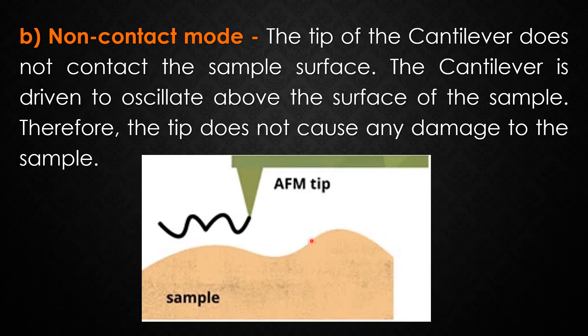Next is the non-contact mode. In non-contact mode the tip of the cantilever does not contact the sample surface. The cantilever is driven to oscillate above the surface of the sample, therefore the tip does not cause any damage to the sample. In non-contact mode the driving motion of the cantilever is either amplitude modulated or frequency modulated.